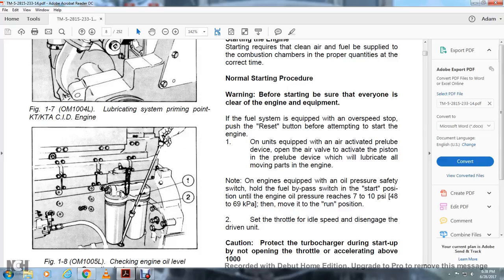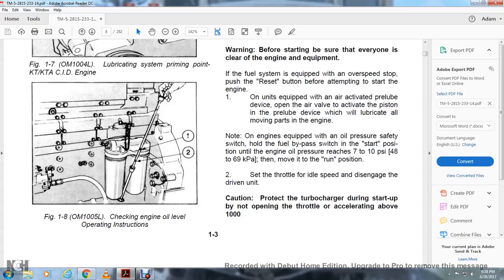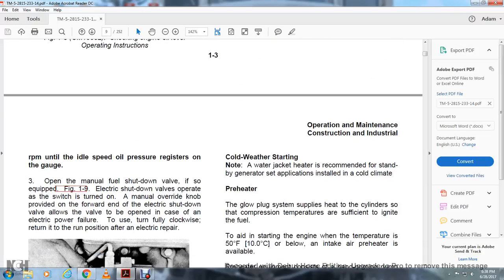Note: on engines equipped with the oil pressure safety valve or safety switch, hold the fuel bypass switch in the start position until the engine oil pressure reaches 7 to 10 psi, then move it into the run position. Set the throttle for idle speed and disengage the driven unit. Protect the turbocharger during startup by not opening the throttle and accelerating above 1,000 RPM until the oil pressure registers on the gauge.